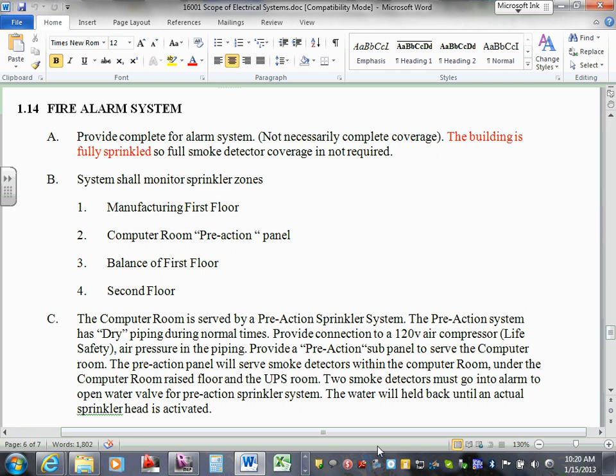NFPA 72. What the fire alarm handbook tells you is where you have to put the system in. NFPA 72 tells you how you have to install it, how it has to be certified, how it has to be tested. The Minnesota State Fire Alarm Code is a book about this big with a bunch of different amendments. Mostly you're going to be looking at section 907. That tells you where a fire alarm system is going to be required in the building.